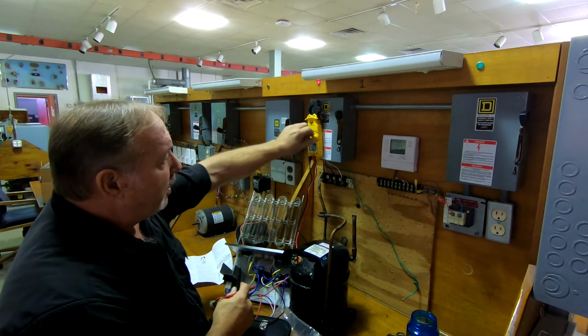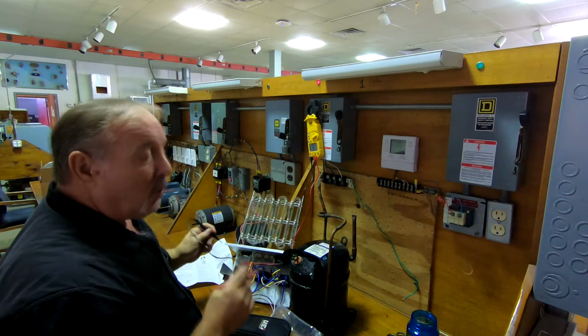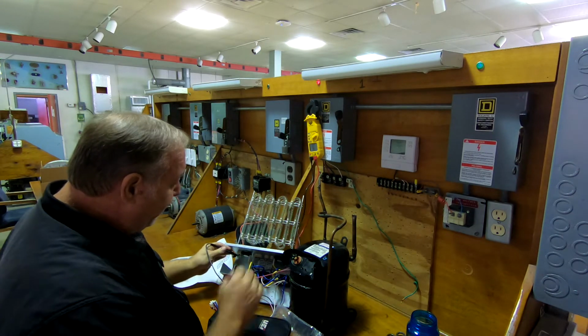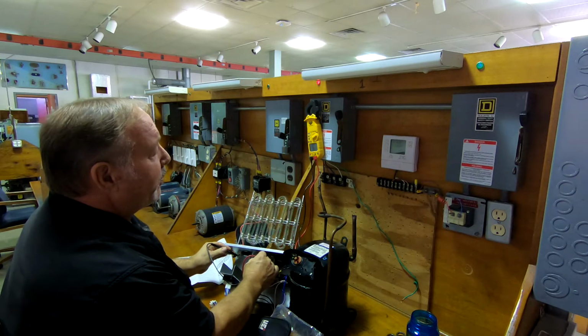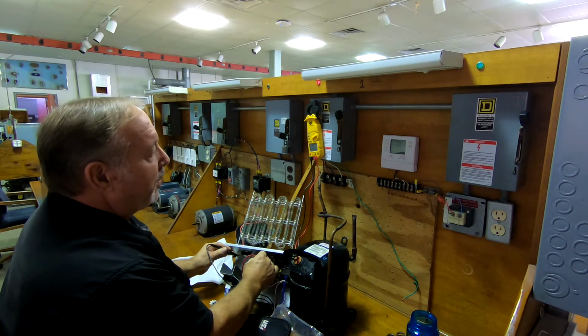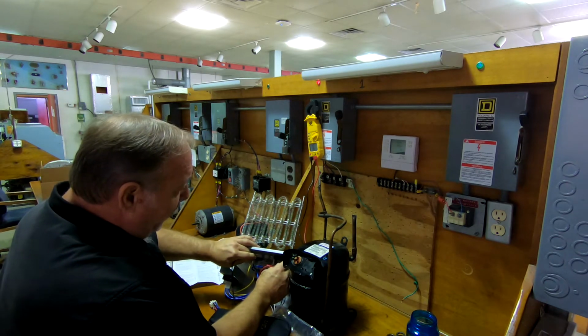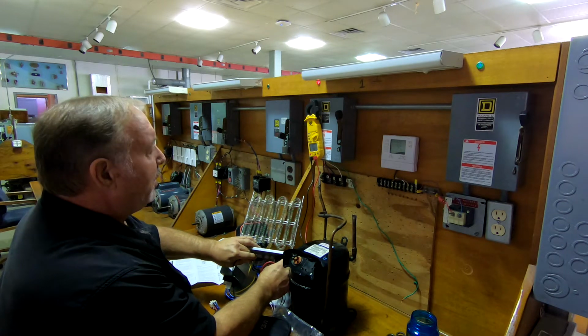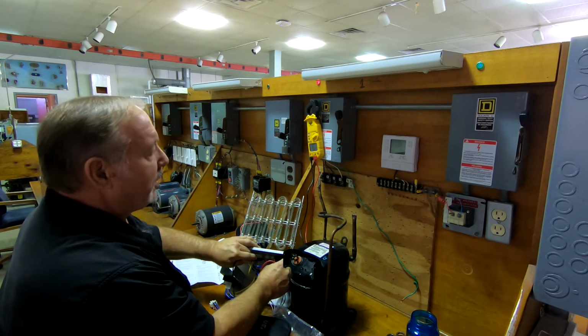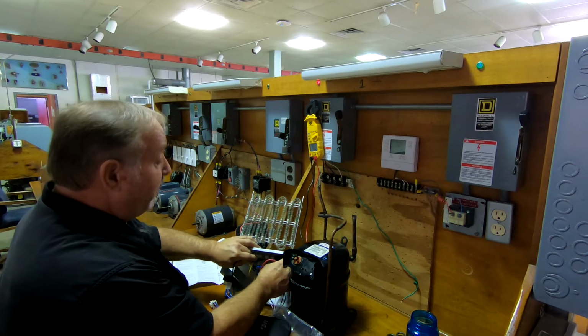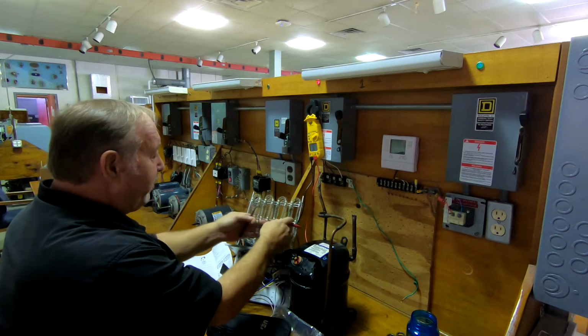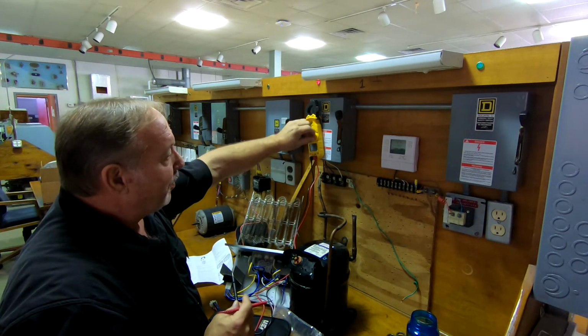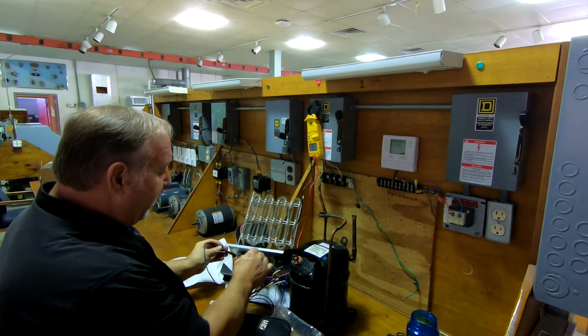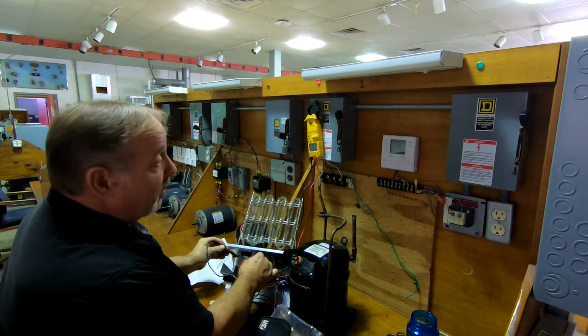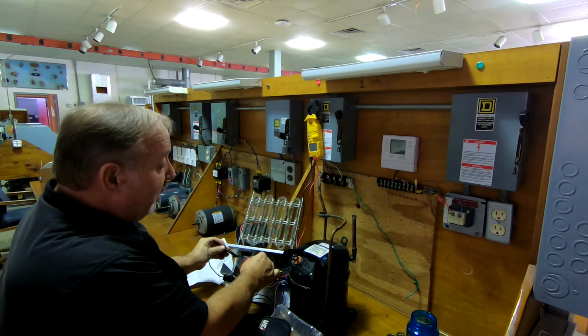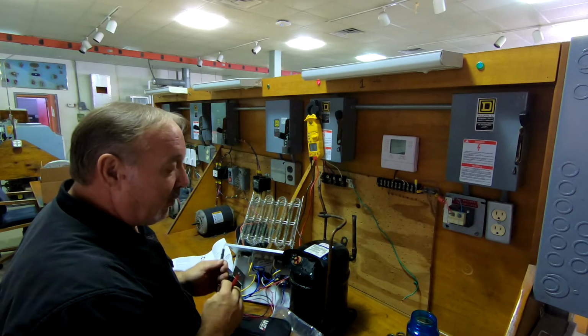So now, let's back one up. This is ohms. So if I want to know what this heater actually has insofar as its resistance, I'm showing 11 ohms. So let me check the second part of the heating element, and we're showing 10.9, 11. So it's accurate. We have two separate sections of this heating coil. That's one way to see it. The other way is you can just use the continuity. So now we know that our heating coil is in good shape, and if we have a problem, it's somewhere else other than the actual coil itself.